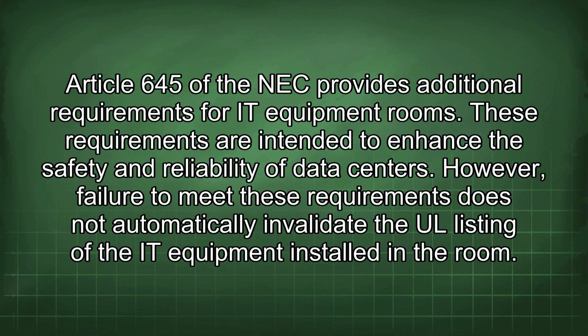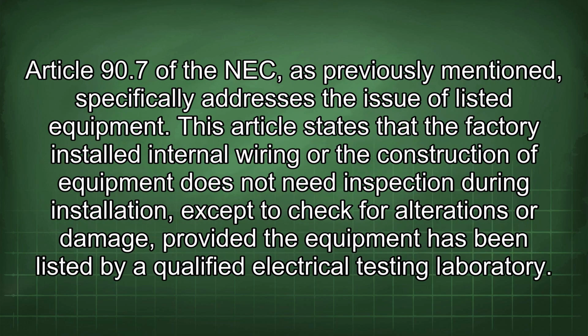These requirements are intended to enhance the safety and reliability of data centers. However, failure to meet these requirements does not automatically invalidate the UL listing of the IT equipment installed in the room. Article 90.7 of the NEC, as previously mentioned, specifically addresses the issue of listed equipment.